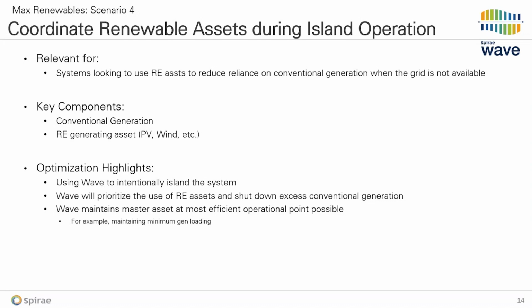So in this scenario, we're going to be looking at conventional generation resources. Again, these could be thought of as your typical diesel backup generators that you might have, and also supplementing those with the renewable energy assets that we've invested in, making sure that, to the extent possible, we're able to offset the fuel consumption of those conventional generation assets with our renewable energy assets, while still maintaining a stable system during island operation, and making sure that we can run that system for as long as possible when we don't know how long the grid may not be available to us.